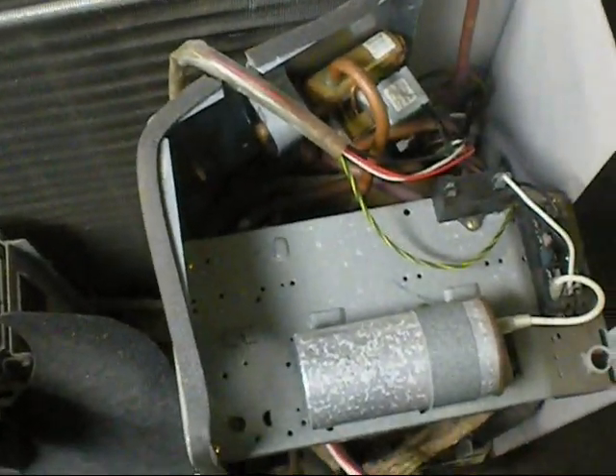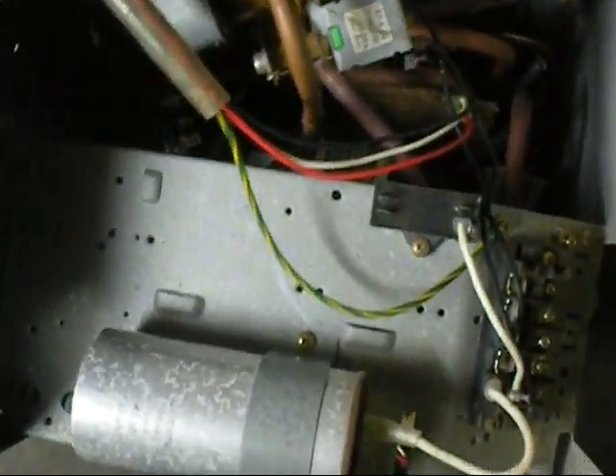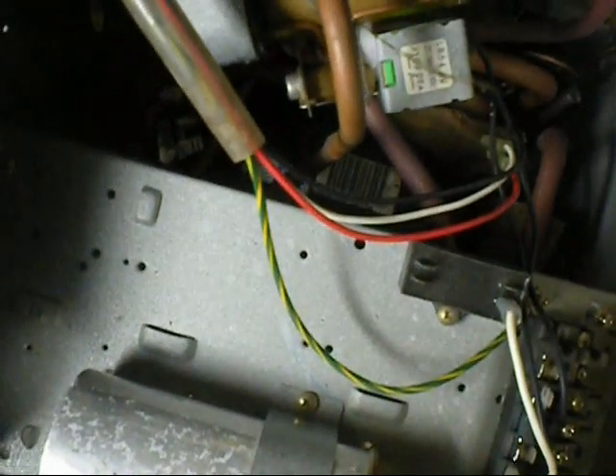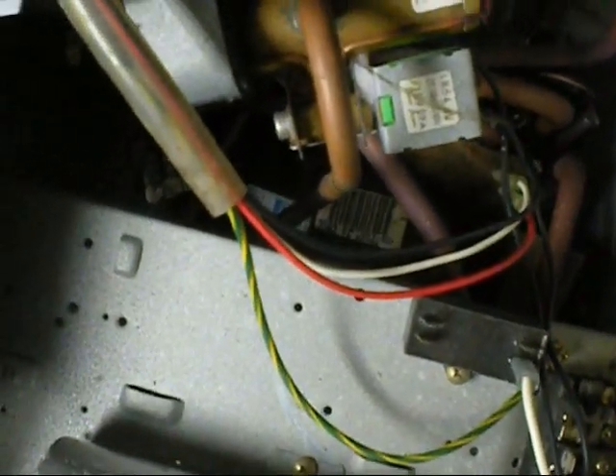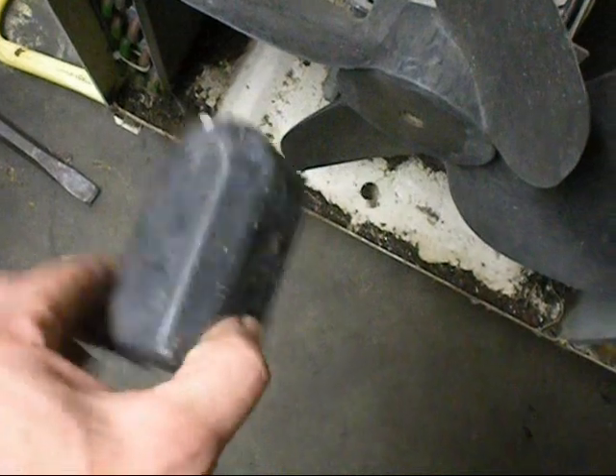So I'll run my meter over it and confirm what I think. I'll probably just have to part this one out and Ed will get the compressor to autopsy, which I figure is the problem with this one. As soon as I took this rattling around I was like, you're dead.